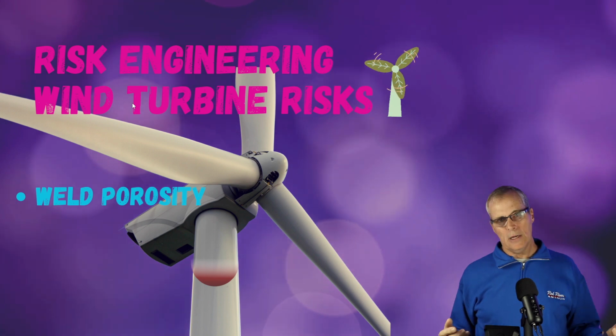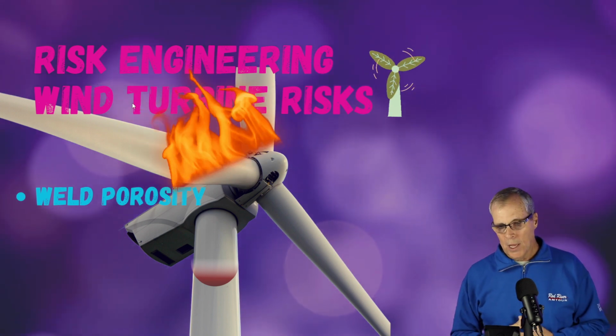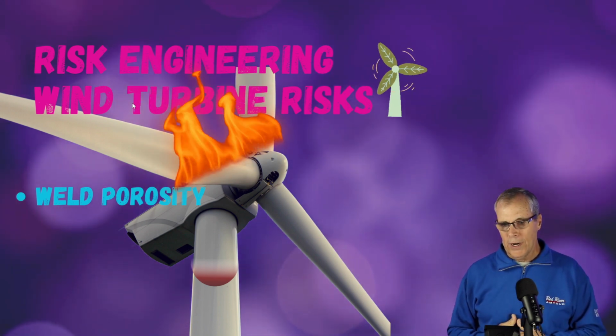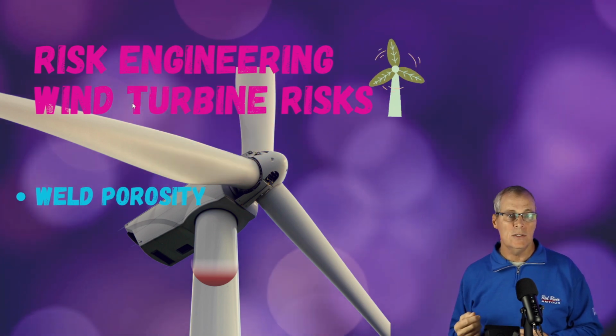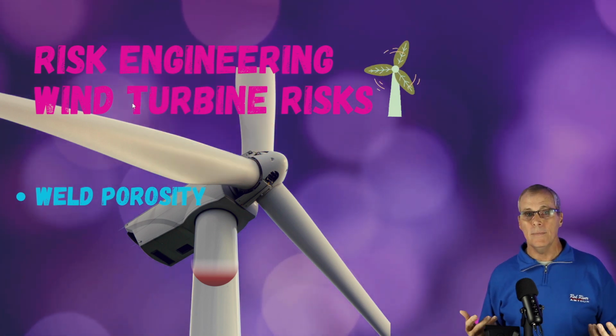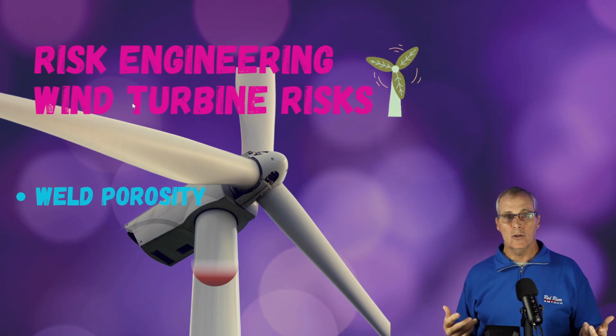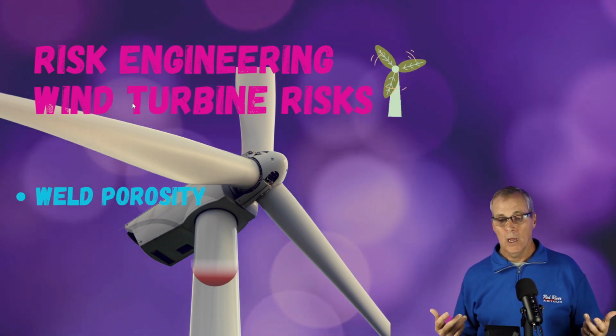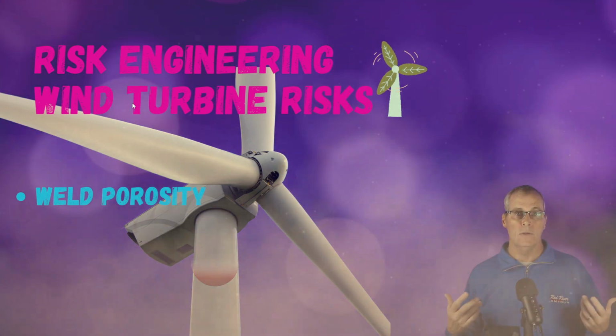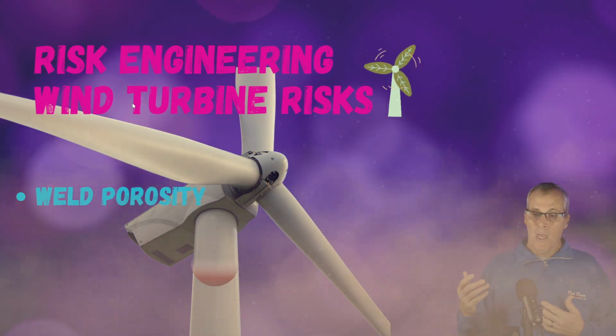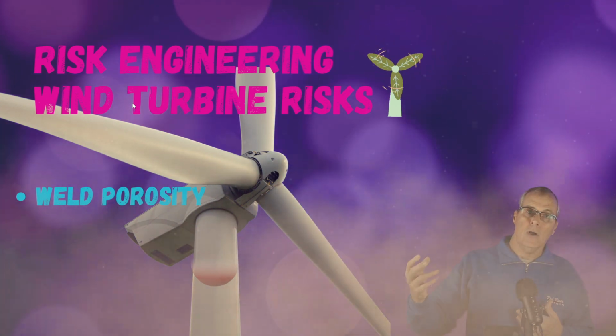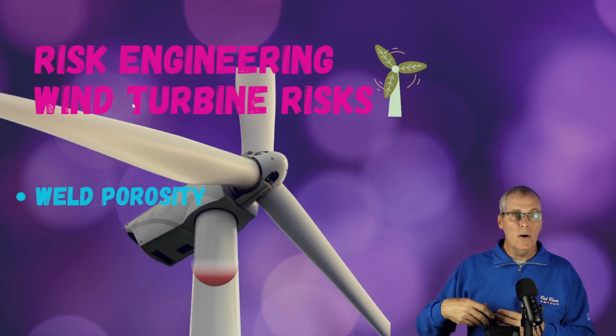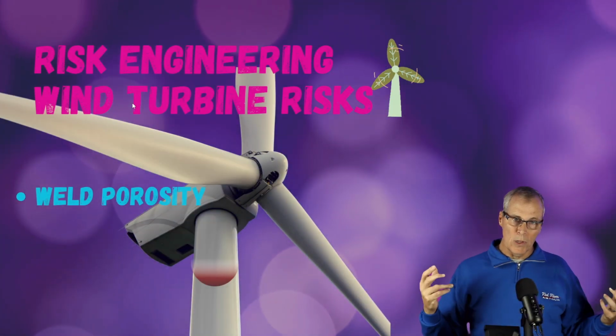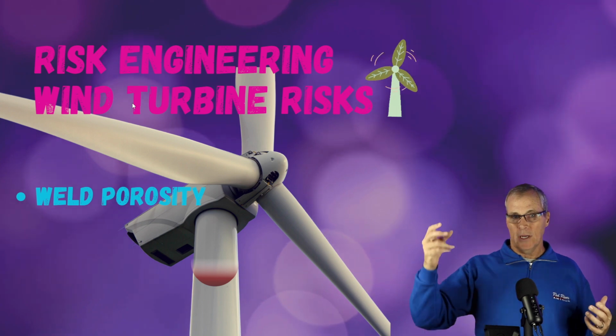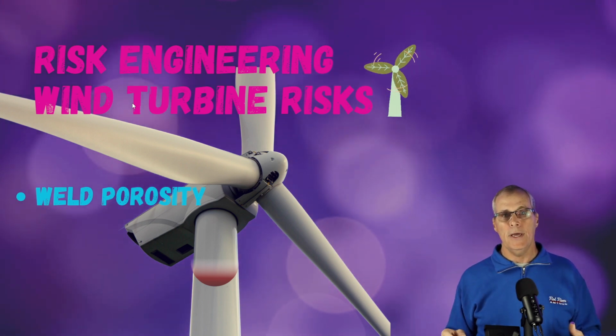We had a fire at a wind turbine. When we got there, what had happened was the HVAC filters had gotten clogged up. It was in Texas, so there was a lot of sand and dust. The filters clog up, the unit overheats, and the electrical equipment starts to burn. The heat of that fire causes the hydraulic accumulator to fail, and oil blows out throughout the inside of the nacelle and all down the inside of the tower.